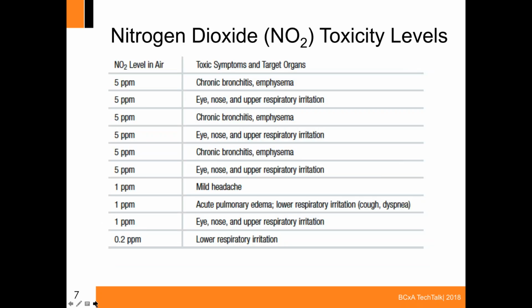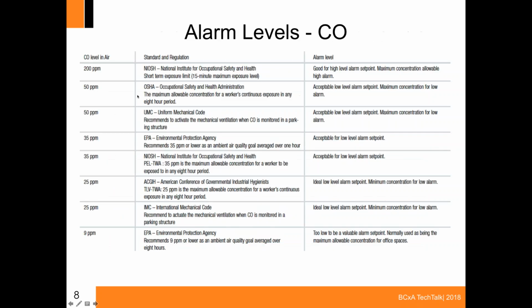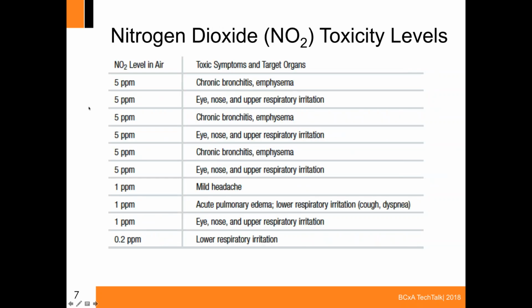For nitrogen dioxide, it's completely different. This one, from the diesel fumes, is far more lethal, and it doesn't take as long an exposure. You can see at as little as 0.2 ppm, you're getting some lower respiratory effects, and as we move up to the 5 ppm, which is actually the calibrated amount, you're getting significant health issues. So what we basically do is alarm at a lower level, or warn, so that you start your ventilation equipment, and then as it rises, we alarm. And we actually alarm somewhere between this 1 and 5, typically at 2 parts per million, so that people aren't getting that.